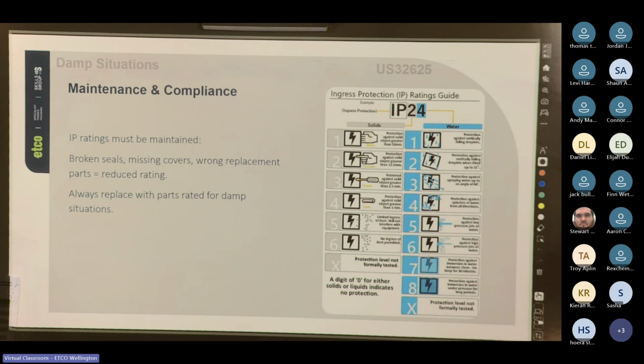If you swap a light fitting seal with a cheap part, you might have just turned an IP44 fitting into an IP20. It might look fine, but it's no longer compliant, which is why most of the time, unless it's an extremely expensive light fitting or it's a one-off fitting, you will just replace the fitting. It is often cheaper and more cost effective to replace the entire fitting and prolong the life of that fitting.